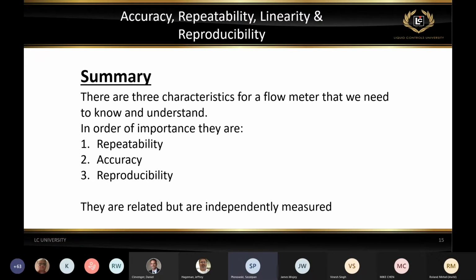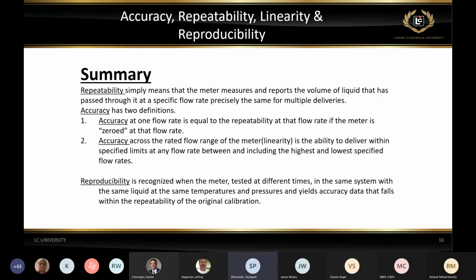Now, if we summarize all those definitions, again, there are three basic characteristics of meter performance, and they're in order of importance. The most important part is repeatability. The second one is accuracy at a single flow rate, but also accuracy across the range of flow, which is more of a linearity, and reproducibility is the last one. Again, they're related to each other, but they are measured independently. So accuracy may depend on repeatability, but they are measured independently from each other.